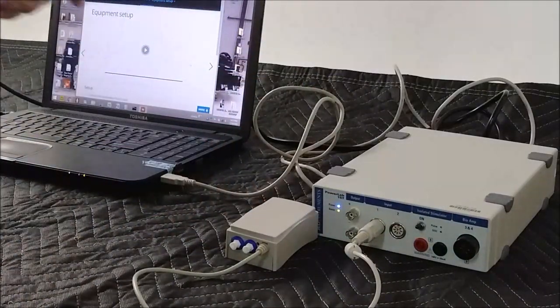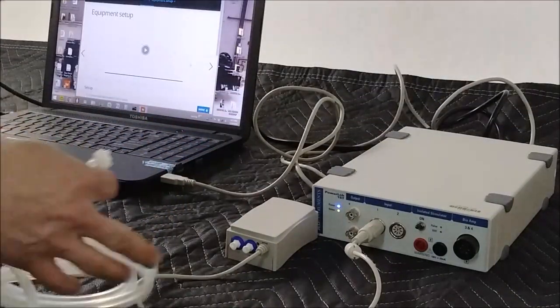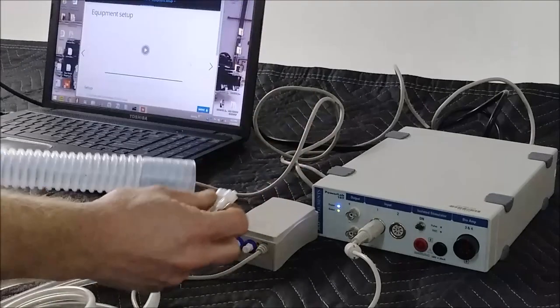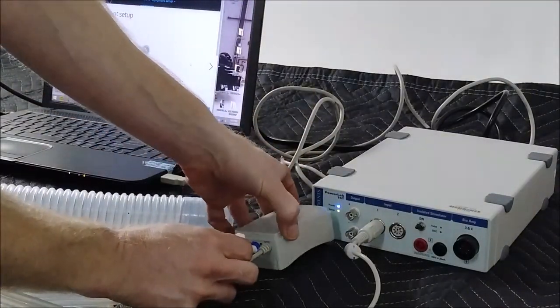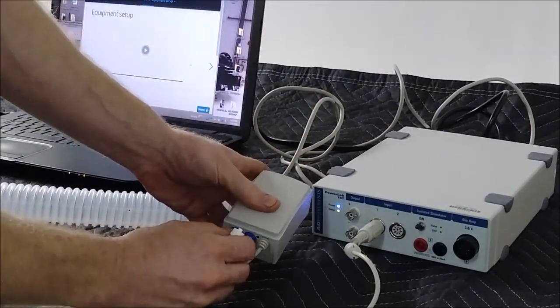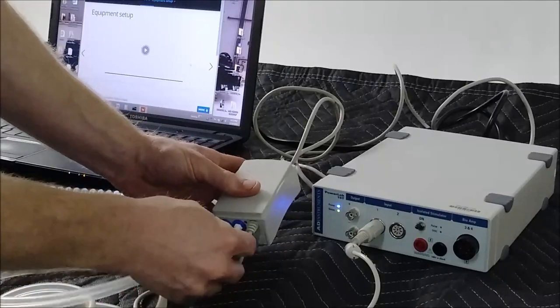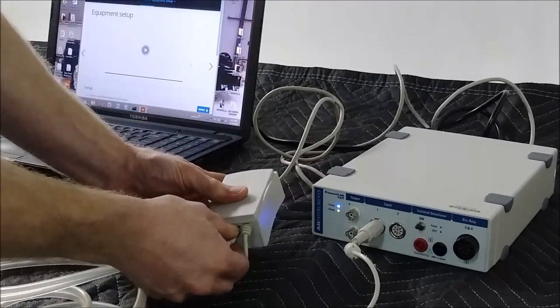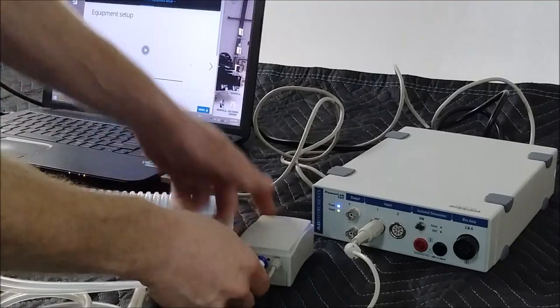Next, we have the spirometry apparatus. Notice the airlines have these two connectors. We're just going to gently push them in and turn them to the right so they lock down on the pod. And we're pretty much good to go with that.